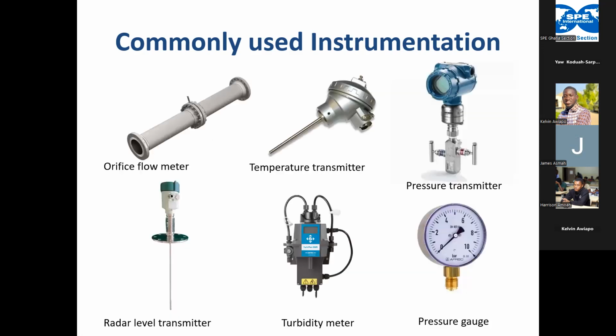I try to show some of them here. The orifice flow: the orifice plate is inserted in between the flanges, and then you read the pressures downstream and upstream of it to be able to measure the flow. And then you have these ones as well: temperature transmitter, pressure, and then radar type level transmitter, and so on and so forth.